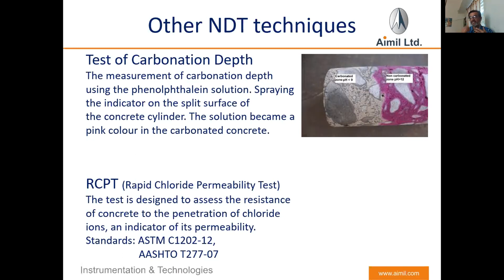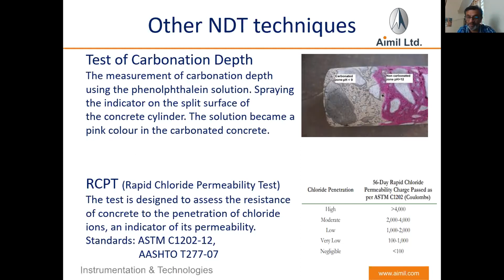In the same way, there is chloride penetration depth. It is RCPT, they call it the rapid chloride permeability test. Again, this instrument gives you an idea about the resistance of concrete against the penetration of chloride. So specifically in coastal areas, you can use this particular instrument to understand the resistance of concrete against chlorination. And chlorination is one of the major causes of corrosion, even more than carbonation. So this is how it gives you an idea with a particular value as per the ASTM code. What is the probability of penetration of chloride ions through the concrete to the reinforcement bar?